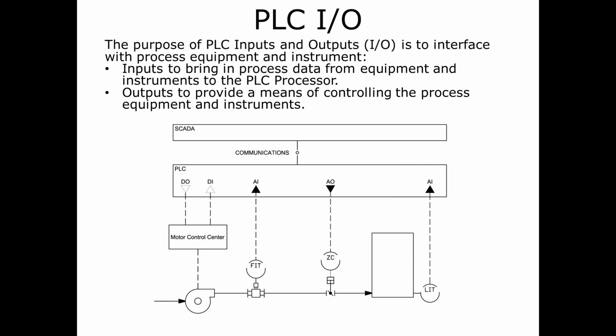I say that, but as I'm saying that, I realize that there is a lot of equipment out there that actually needs to send information to the PLC to give an update of the status. For example, you'll have a pump that sends a signal to the PLC to tell you that it's running, or you may have a valve that is opening or closing, and it's telling the PLC how open or closed it is. But the outputs are the data coming from the PLC. The inputs are the data going into the PLC. And that's basically the difference between the two.